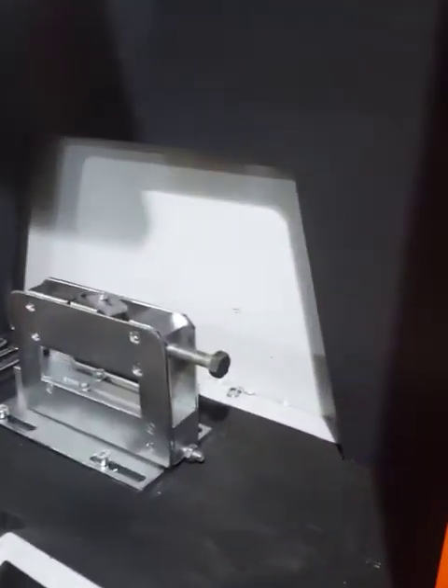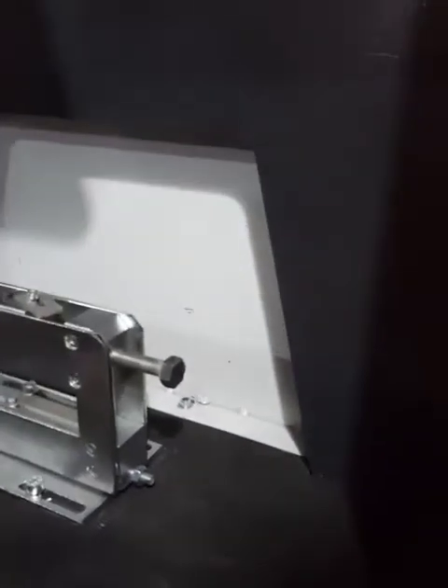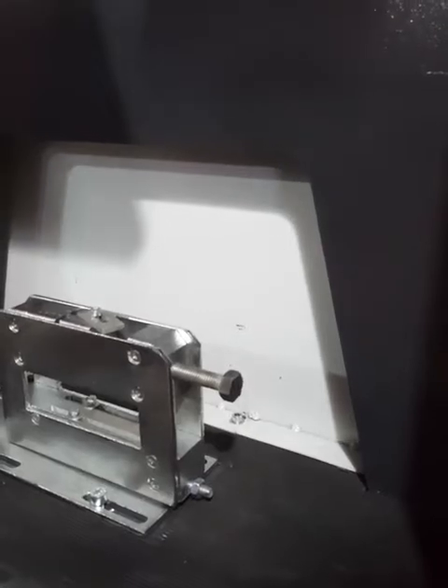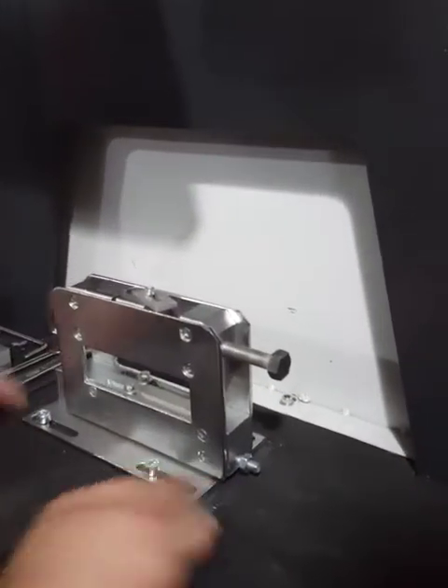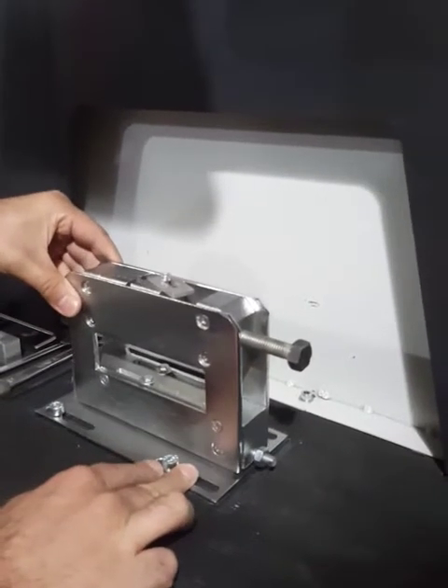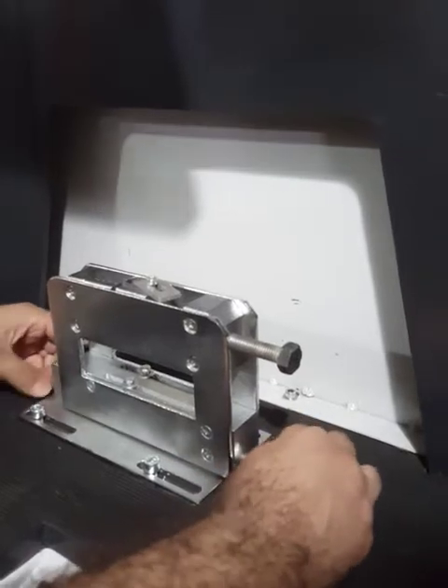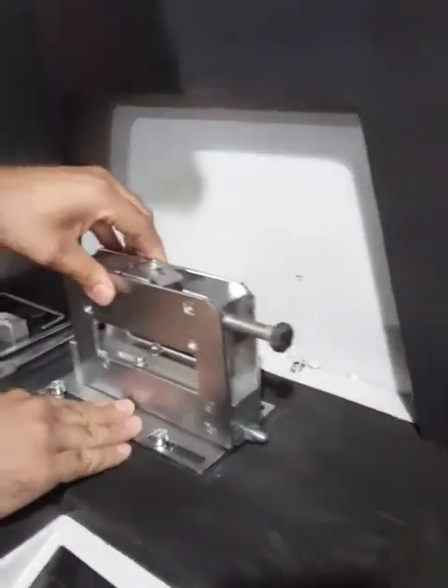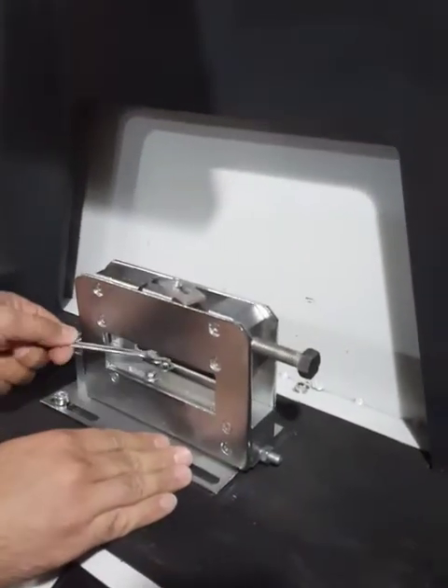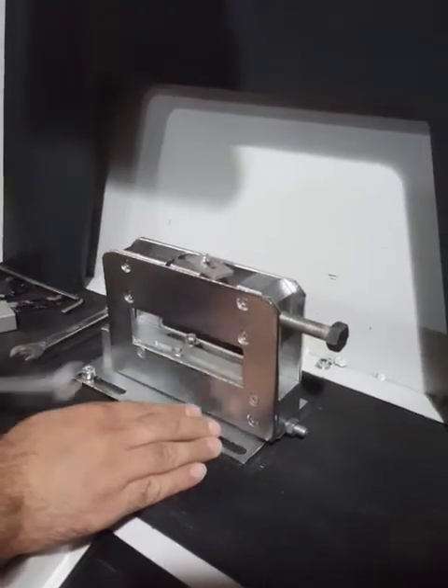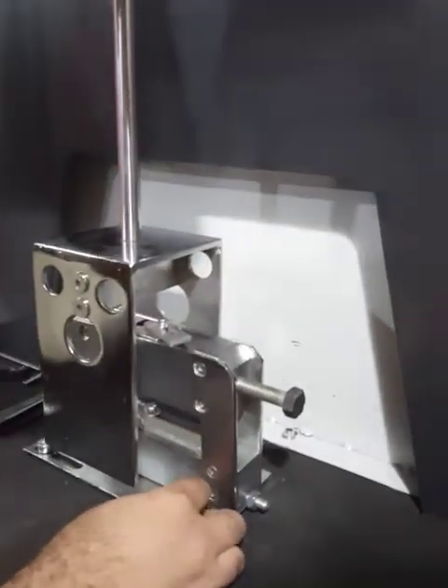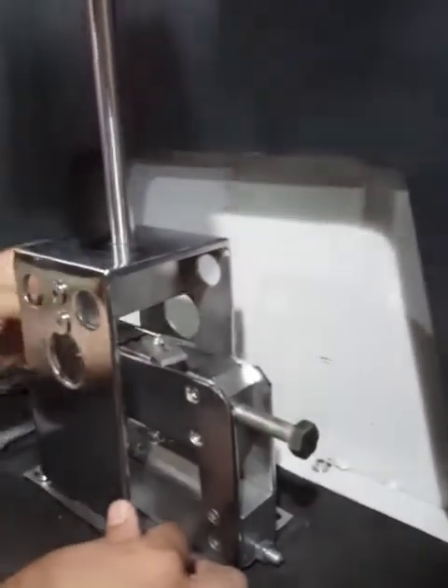Here in the sample gripper section we have a fixture moving in two directions, left and right, and the gripper itself is moving up and down using two wedges sliding on each other. How we need to adjust the height is in this way. You see, we have an impact point of the pendulum. Here is the impact point of the pendulum.